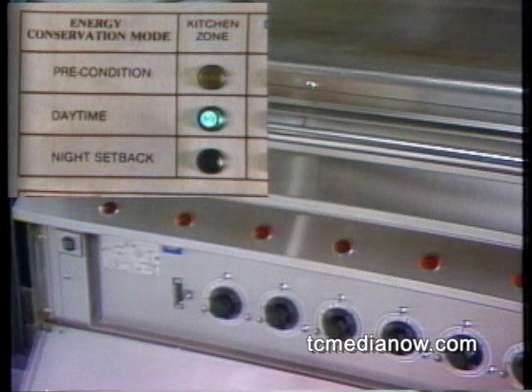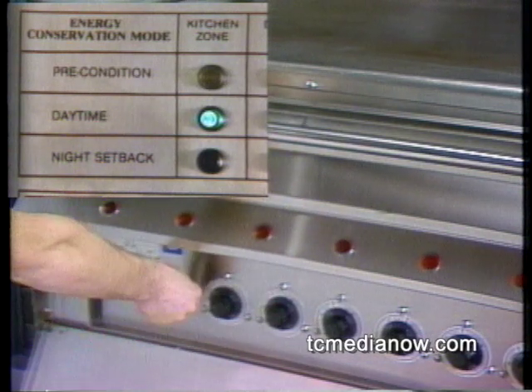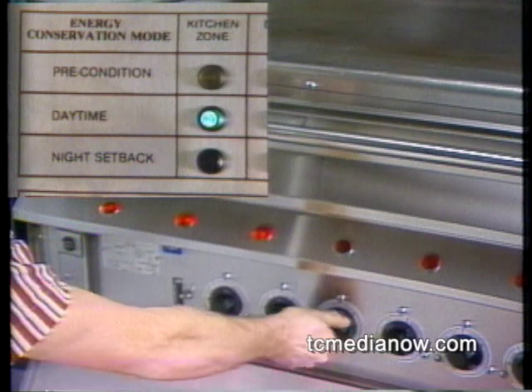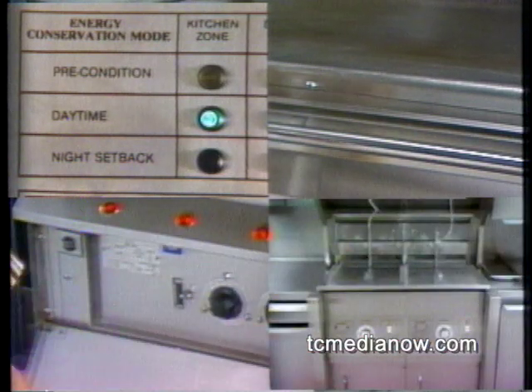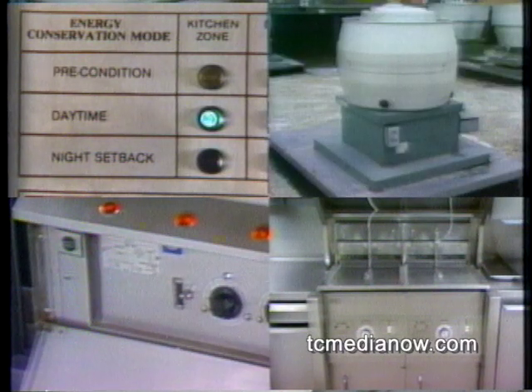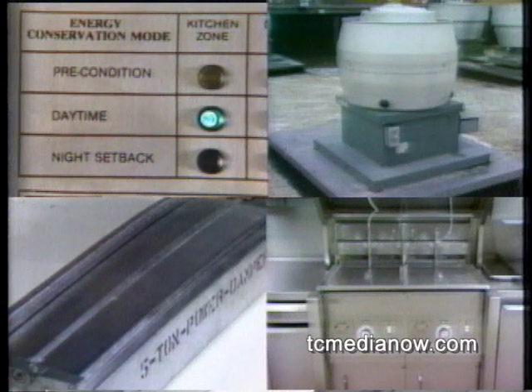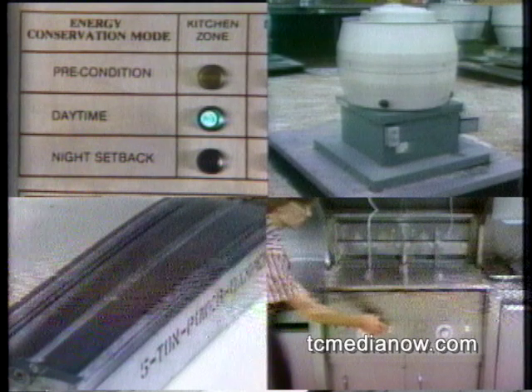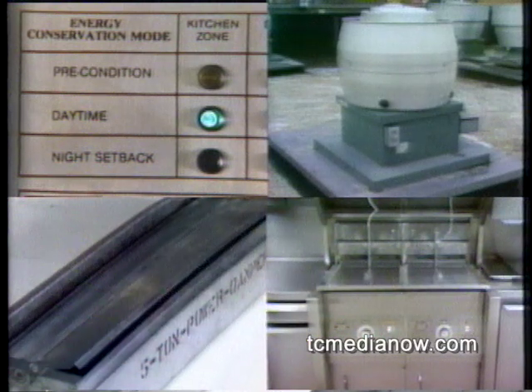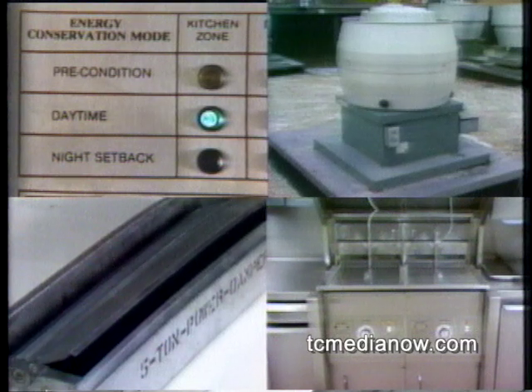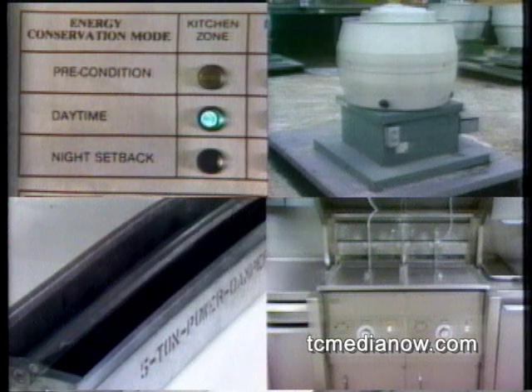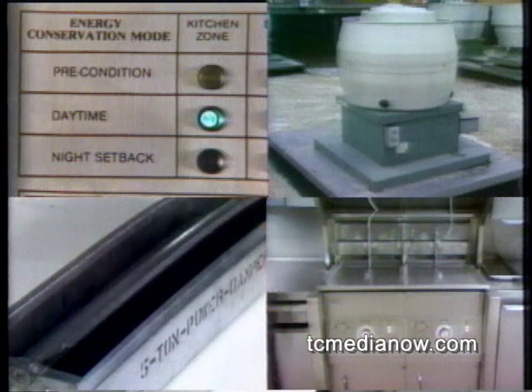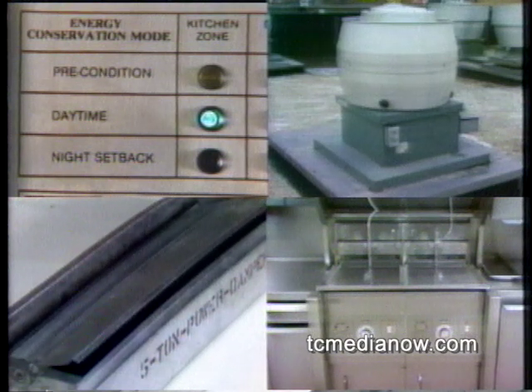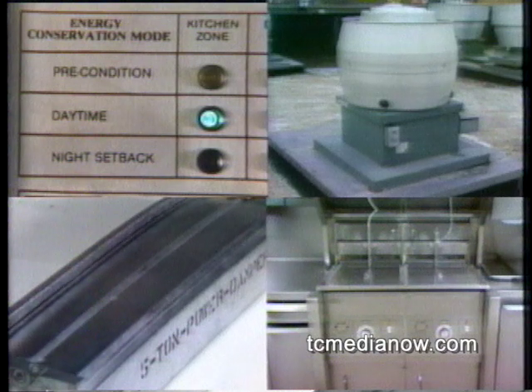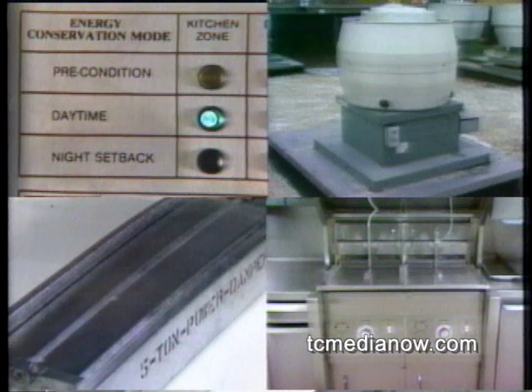In the daytime mode, the HVAC units are fully operational, and power is made available to all cooking equipment. The system's main function in the daytime mode is to interlock each piece of cooking equipment with the exhaust fan that serves it, and with HVAC outside air dampers as well. When a cooking unit is turned on, the exhaust fan that serves that unit is automatically turned on as well. Also, outside air dampers in the HVAC system open as needed to provide the necessary makeup air. When the cooking unit is turned off, the exhaust fan is automatically turned off, and the proper HVAC damper closes. This assures proper exhaust levels, while the amount of makeup air that must be heated or cooled is kept to a minimum.